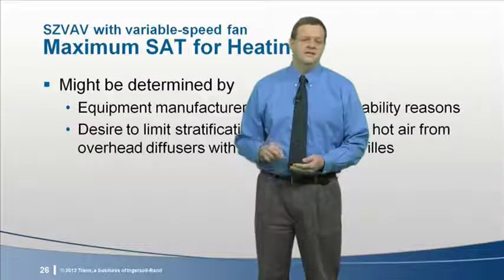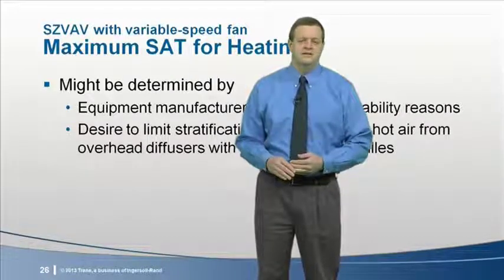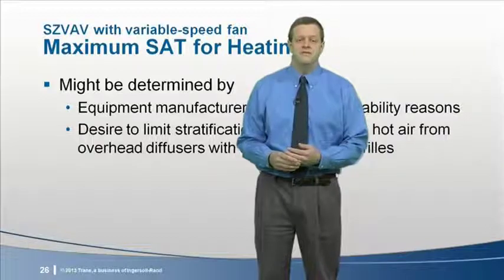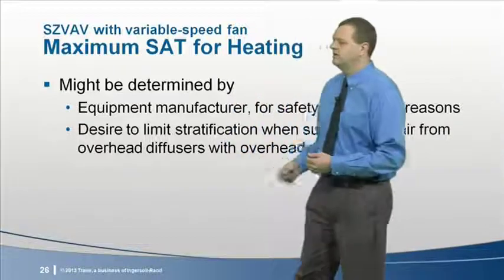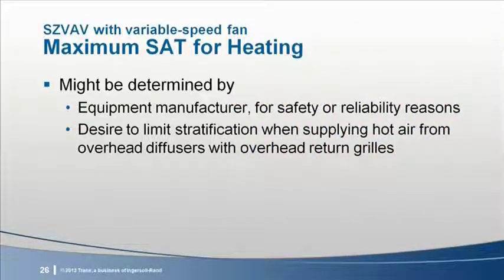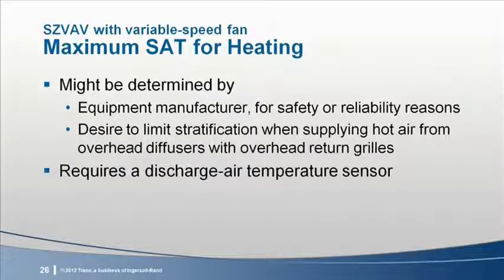One way to avoid or limit this effect is to deliver the air at a not so hot temperature during heating. In this case, the maximum supply air temperature for heating might be set to 15 degrees above the zone set point. One additional comment. Controlling this type of maximum limit requires a discharge air temperature sensor be included in the equipment.